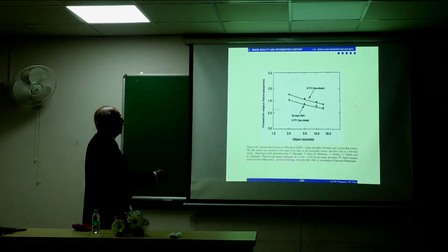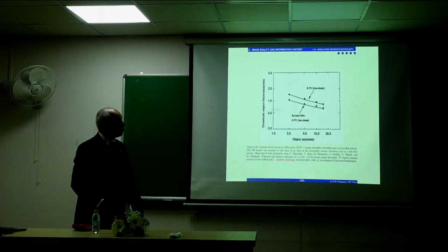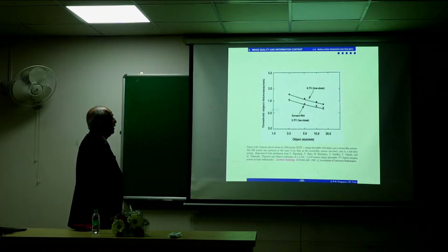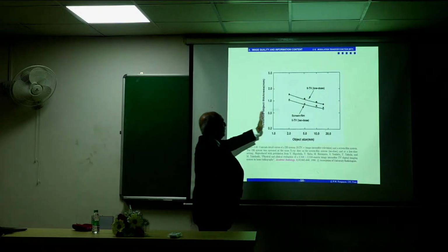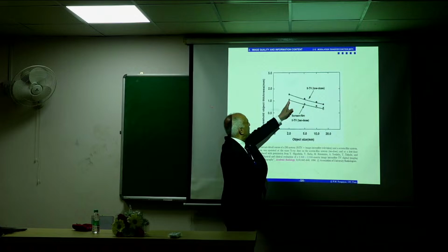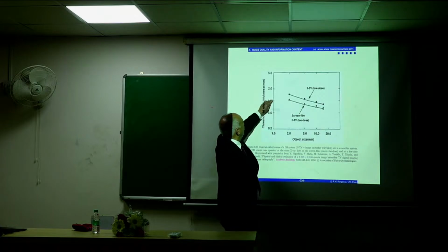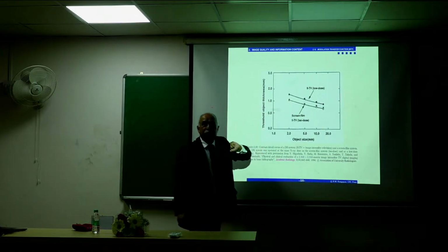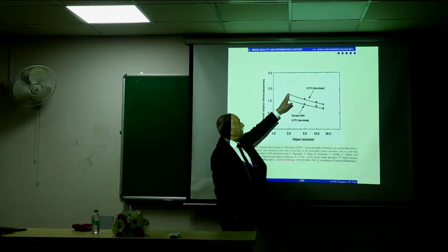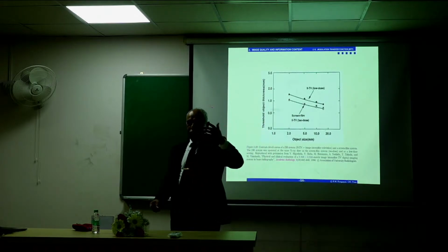And then for different imaging systems, the image intensifier TV digital radiography system, screen film system, they plotted these curves. So for a given object size, with the screen film, you can detect thinner objects. With the digital system, the object has to be thicker in order to be detected.